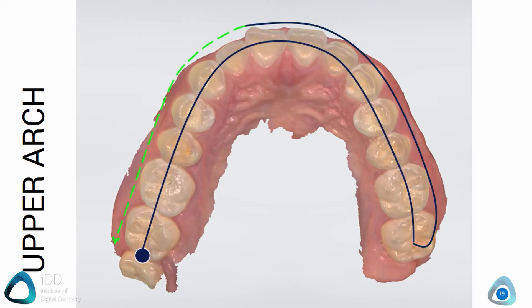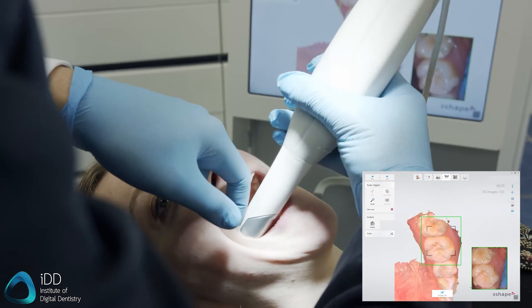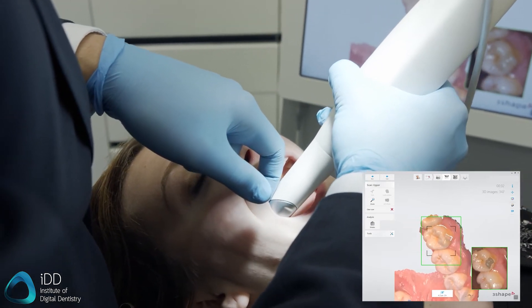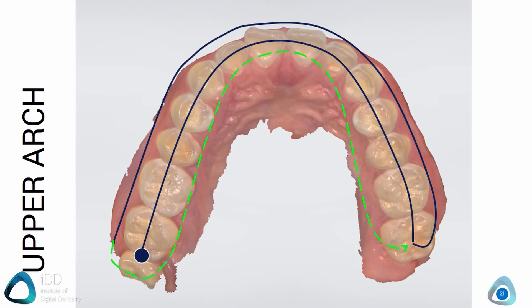Once you reposition, move towards the posterior aspect comfortably. As you reach the midline, stop the scan, reposition, and then start again in an area where there is already data — the scanner will recognize this and continue the process, putting your hand in a much better position. Finally, once you reach the posterior aspect, tilt the scanner across the occlusal surfaces and scan the palatal aspect from the posterior molar of one side to the other. That is your full arch scan, which can take under 40 seconds — compared to three to five minutes with a PVS impression.